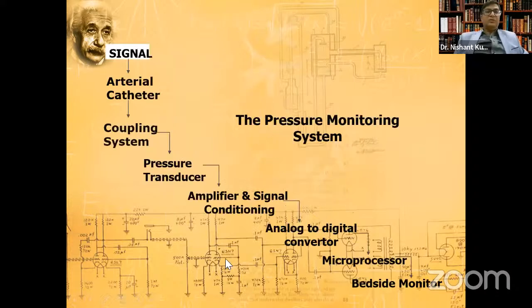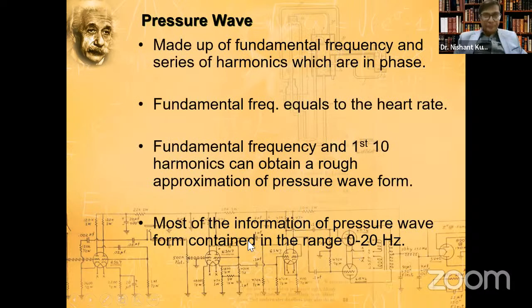So the signal from the arterial catheter goes to the coupling system, that is the tubing and pressure transducer, where it is amplified. As I said, the current is produced and amplified, and the analog is converted to digital, which gives us the waveform and the number via the microprocessor, and ultimately the image is displayed.